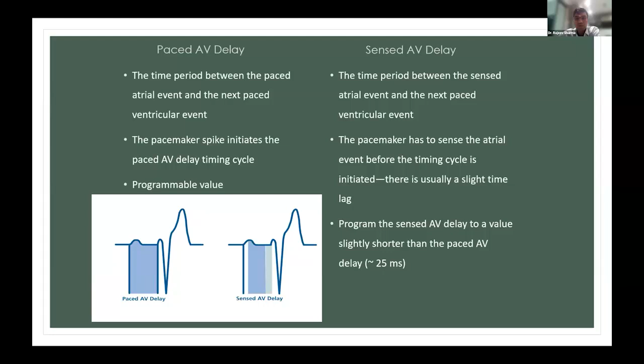So there is a time lag. That's why a sensed AV delay is usually programmed shorter than a paced AV delay, because we have to cover the delay of sensing the atrial signal from the pacing electrode. So it is usually 30 milliseconds. So what is the clinical importance of this paced AV delay?